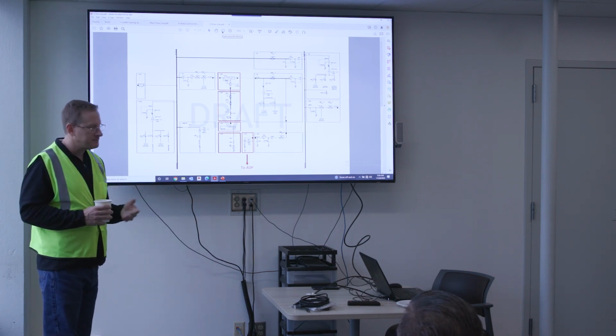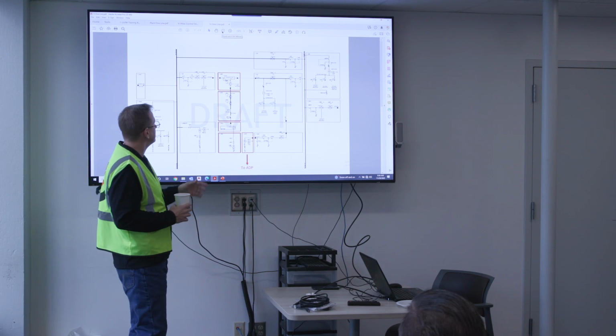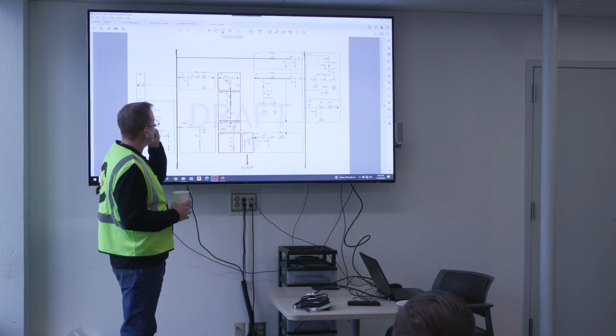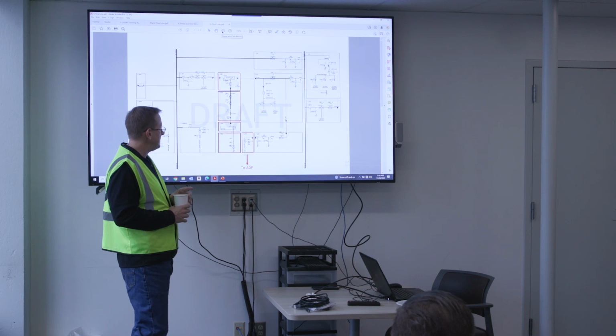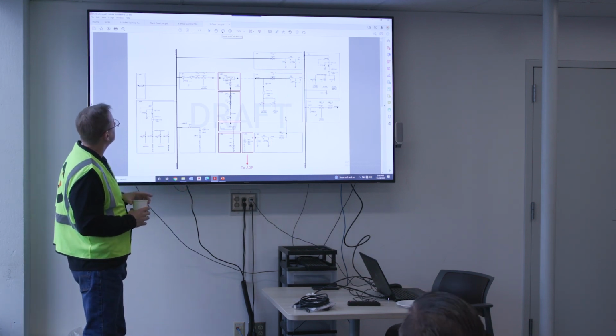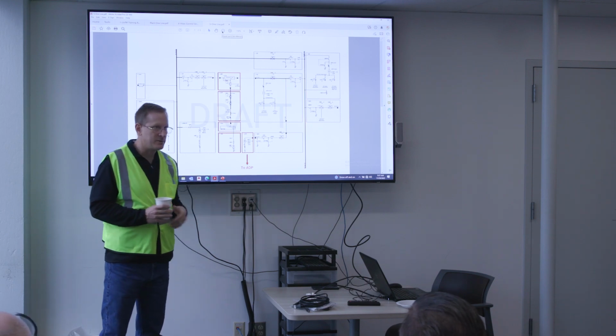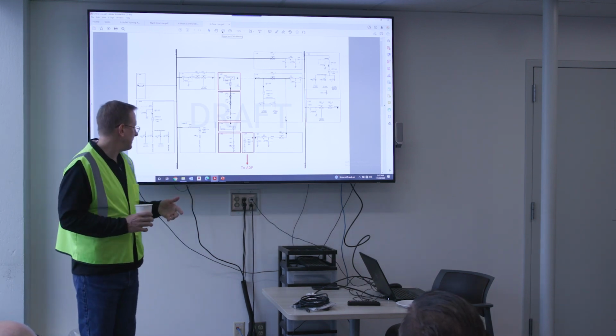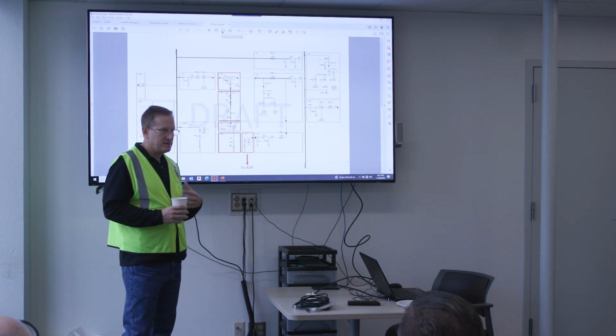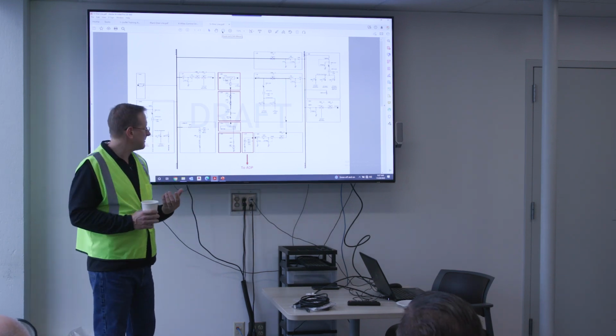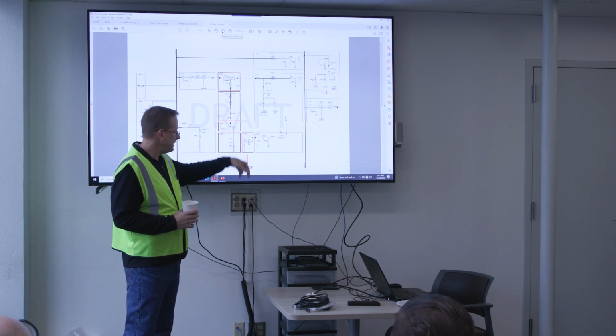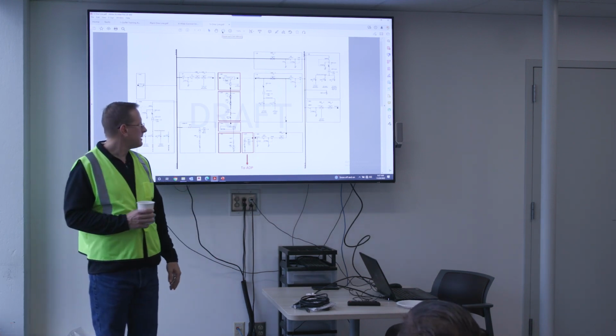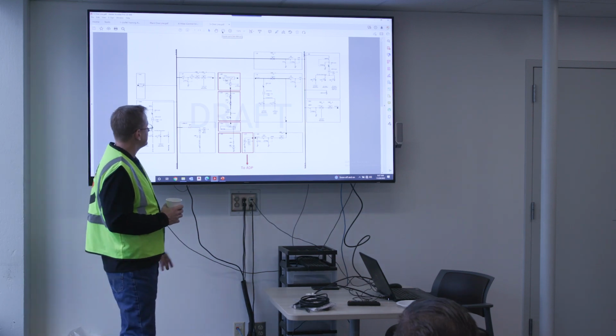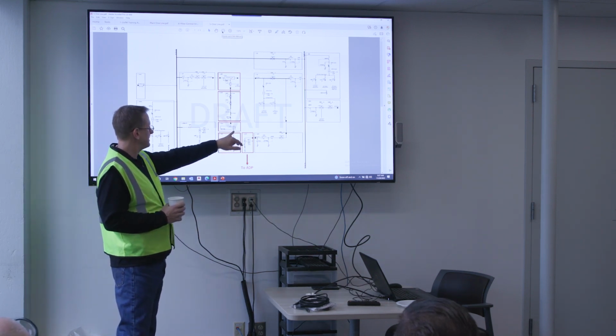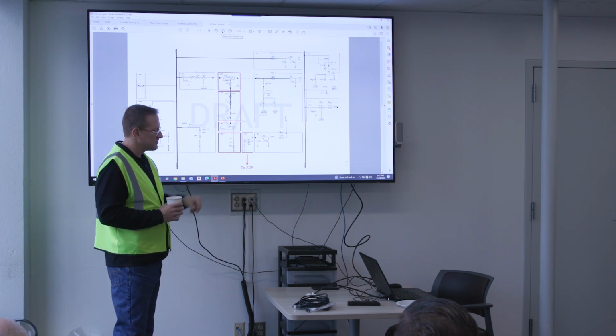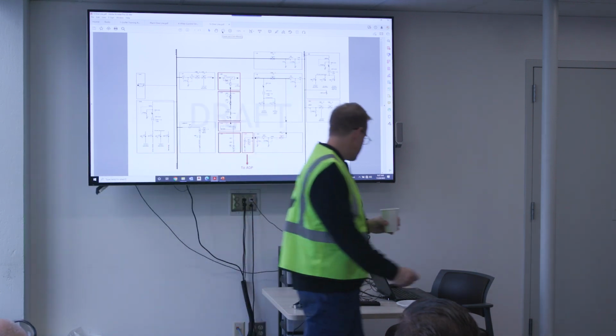The UCP is another panel. As I mentioned, the UCP is what basically controls the flywheel. And the UCP is also fed from the ADP as well. So it's a low voltage panel. For example, the power that is given to the pony motor to charge the flywheel comes from the ADP feed into the UCP. And I talked about the RSP panel as well, which is the 24-volt starting system for the diesel. It is also fed from the ADP on the low voltage auxiliary side.